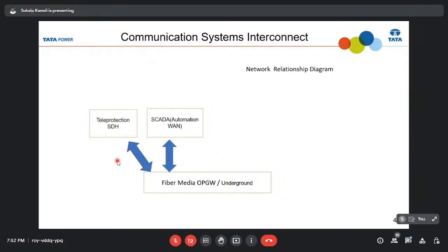Any electrical system, whether at low or higher voltage, requires grounding, and that conductor serves as a medium for it. But more than that, inside that conductor we have optical fiber running, 48 core, 96 core fiber. These OPGW fiber optic cables traverse across all receiving stations in Mumbai, giving communication connectivity across the Mumbai license area, right up to our hydro generating stations. This fiber optic network of OPGW and underground fibers forms the backbone of the applications I'm presenting here.